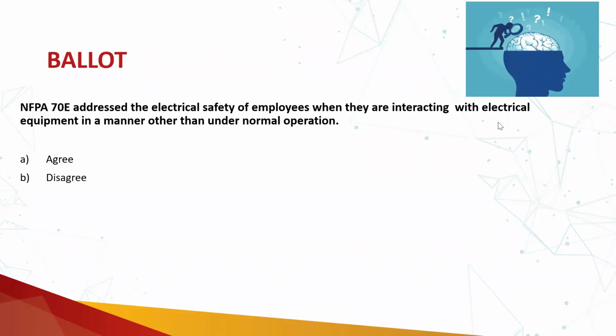This is an agree statement because all the requirements of NFPA 70E apply when the equipment is not considered under normal operating condition. So we have seen that if the equipment is considered under normal operating condition, that means the equipment has been properly maintained, it has been installed correctly, there is no evidence of impending failure, no doors are open, and so on. So 70E requirements are not in place.